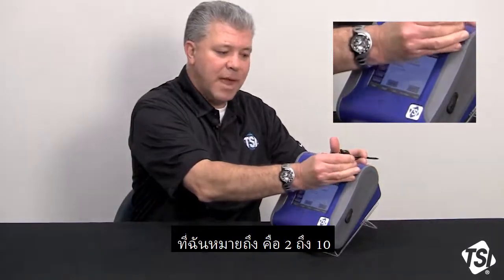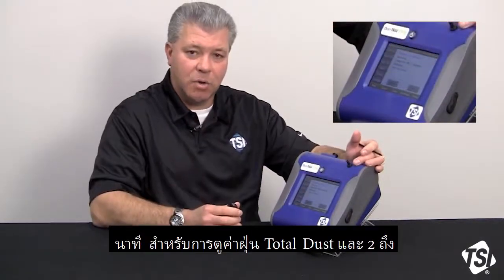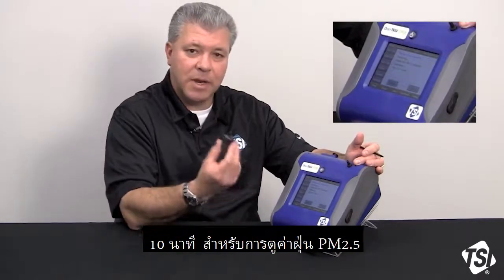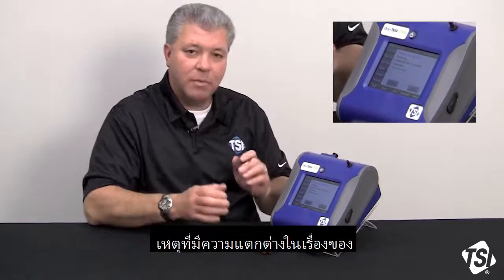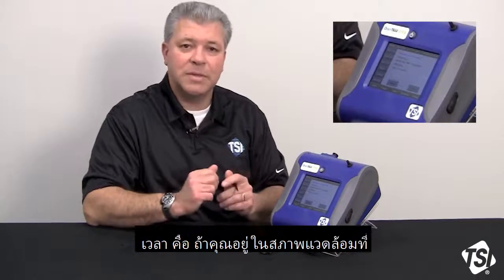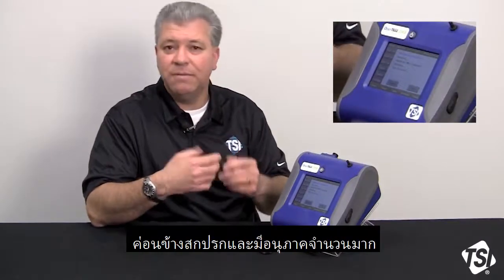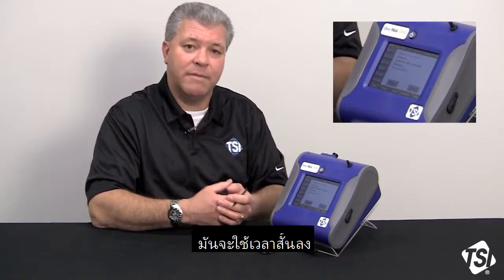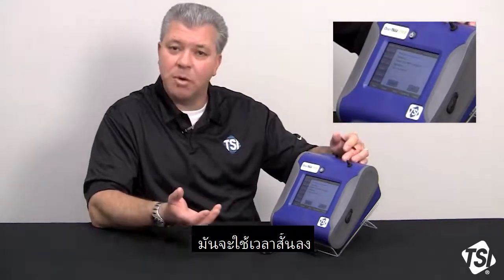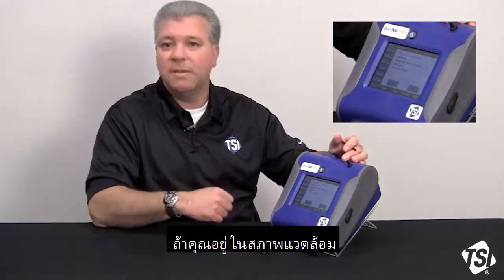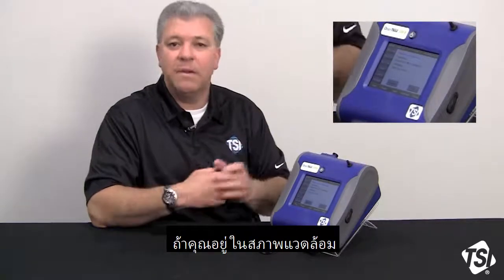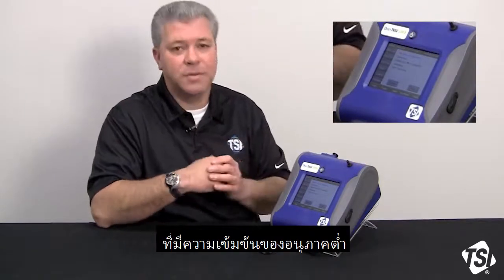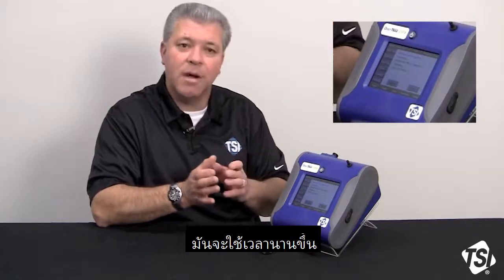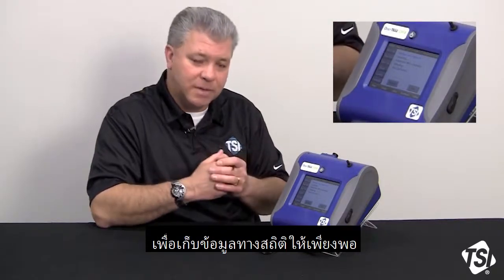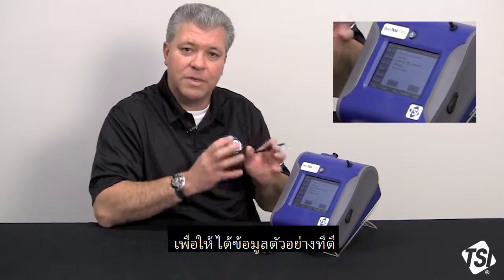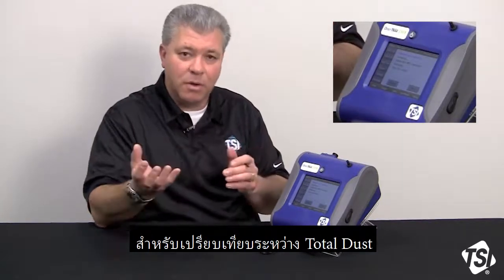So what I mean by that is 2 to 10 minutes looking at total dust and 2 to 10 minutes looking at PM 2.5. The reason for the difference in the time is if you're in an environment that is, say, fairly dirty, okay, has a lot of aerosol, it's going to take a shorter period of time to get a statistically valid sample. If you're in an environment that has a very low concentration of aerosol, it's going to take a longer period of time to get enough statistical information to give us a good sample base to compare the total versus the PM 2.5 fractions.